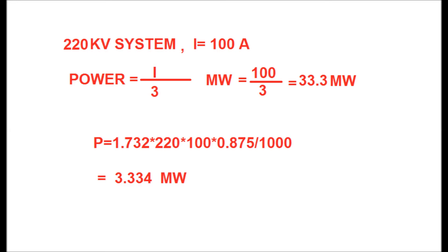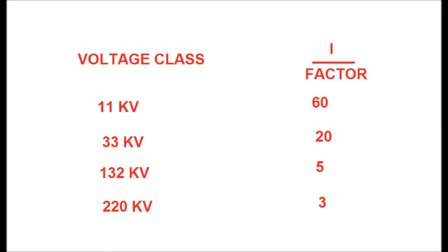So what should be the factor for different voltage classes is shown in this figure: for 11 kV, divide by 60; for 33 kV, divide by 20; for 132 kV, divide by 5; and for 220 kV, divide by 3 — to get the power in megawatts for whatever value of current.